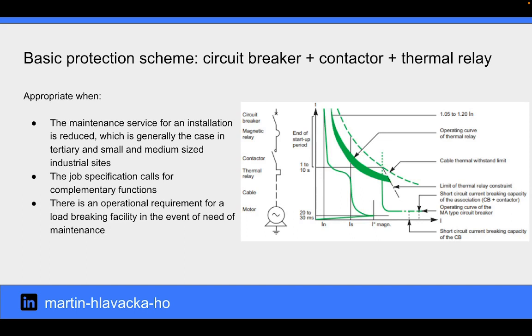The combination of a circuit breaker, contactor, and thermal relay for the control and protection of motor circuits is eminently appropriate when the maintenance service for an installation is reduced, which is generally the case in tertiary and small and medium-sized industrial sites. The job specification calls for complementary functions. There is an operational requirement for a load breaking facility in the event of need of maintenance.